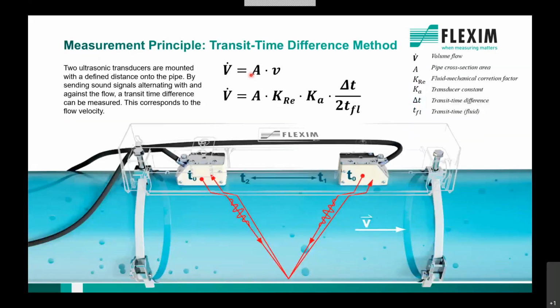The measurement principle, for those who are not familiar with it, is the transit time difference method. That means we clamp our transducers on from the outside of the pipe. We send a signal upstream and downstream with the flow. And when there is flow, the signals show two different travel times. We basically measure the time difference of both signals, upstream and downstream. Multiplied with the pipe cross-section area, we get the volume flow. The formula will come up twice more in the following slides, where we will talk about it and what the effects are.